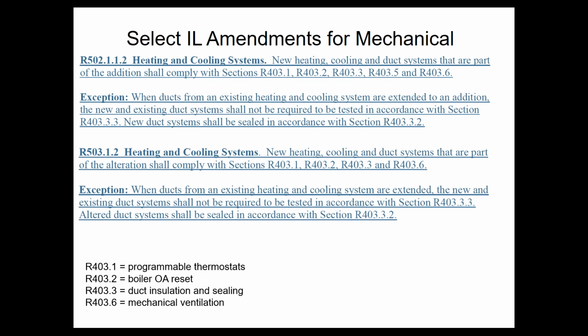There are a few other amendments in Illinois. For the most part, the quick summary is that no matter what you do, on new construction, you've got to do everything. On equipment changeouts, you're going to have to do the programmable stat. You're going to have to add the boiler controls. You're going to have to insulate and seal any new ductwork that you have. And you're going to have to do mechanical ventilation.